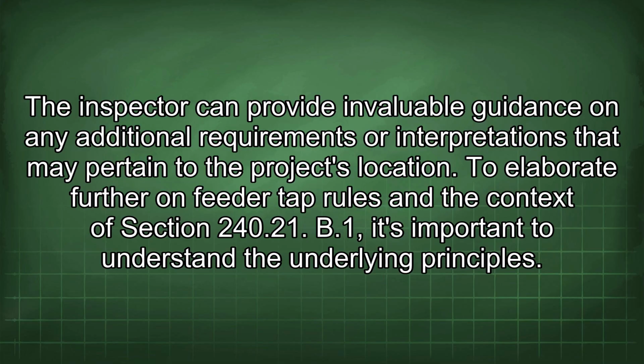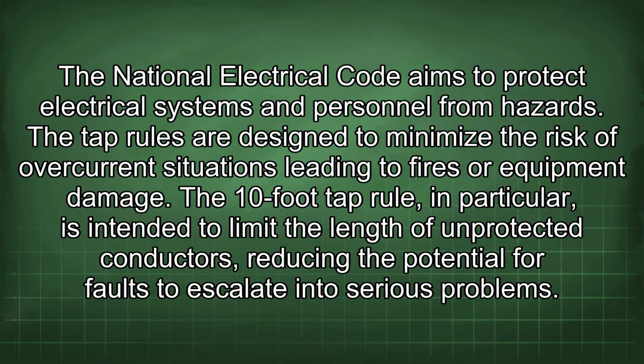To elaborate further on feeder tap rules in the context of Section 240.21.B.1, it's important to understand the underlying principles. The National Electrical Code aims to protect electrical systems and personnel from hazards. The tap rules are designed to minimize the risk of overcurrent situations leading to fires or equipment damage. The 10-foot tap rule, in particular, is intended to limit the length of unprotected conductors, reducing the potential for faults to escalate into serious problems.